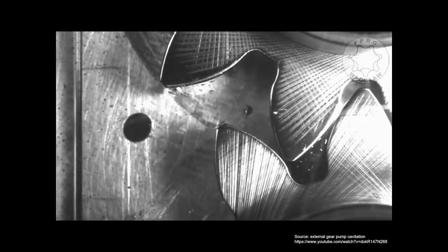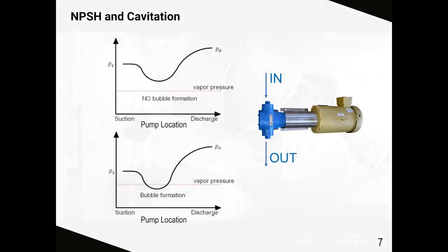To prevent cavitation, we must stay above the vapor pressure line. In a fuel oil system, operating in a vacuum condition on the suction side of a pump, we end up with an elevated vapor pressure line, which facilitates cavitation in an improperly designed system.